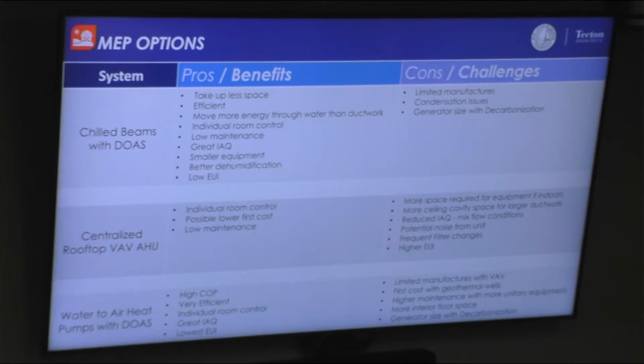Individual room control. Every single room has their own control. Great IAQ. Each space gets a dedicated outside air delivery to operate through the chill beam. So your indoor air quality, your ventilation is designed for the room, and it's always fresh. There's no mixed use type ventilation where you're taking return air and recirculating it back in. It's always 100% outside air. Smaller equipment, better for dehumidification because we can control the temperatures, and a very low energy use intensity, as I mentioned.